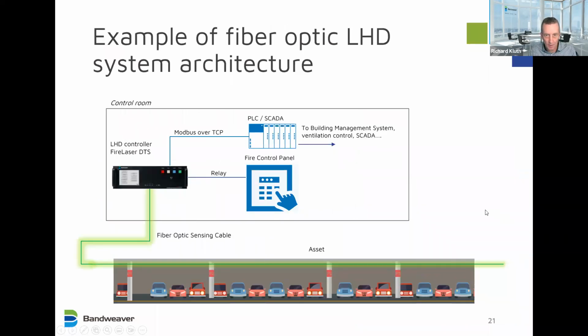This is a very typical system architecture for fire detection. You've got the unit, which will be in a control room, a rack, or a wall-mounted unit. You then have the cable going out to the field. As we said, a single cable, that's the only element you need to install. The relays connect to the fire control panel, and often communications to SCADA, Modbus over TCP, to PLC, to building management system, ventilation control, SCADA. And some of our examples later will show examples of that. In addition to fire alarm information, you can also get absolute temperature data, which can be extremely useful.